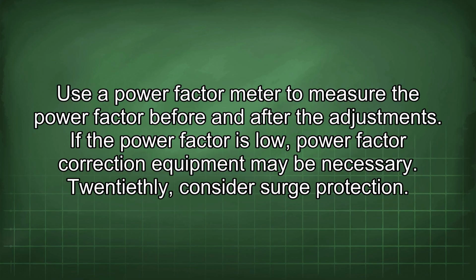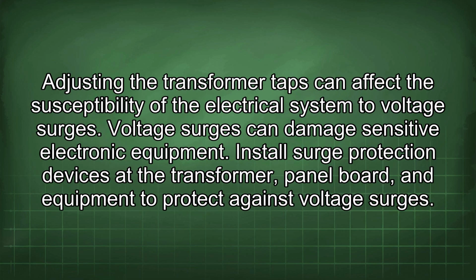20thly, consider surge protection. Adjusting the transformer taps can affect the susceptibility of the electrical system to voltage surges. Voltage surges can damage sensitive electronic equipment. Install surge protection devices at the transformer, panel board, and equipment to protect against voltage surges.